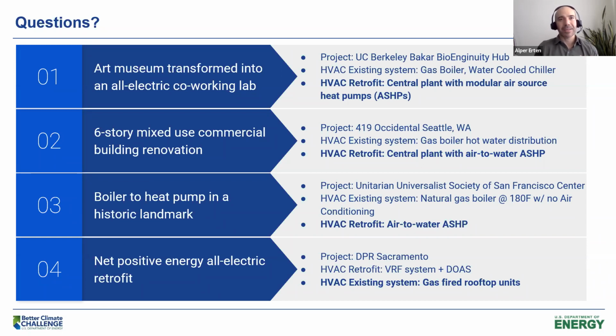In terms of the conversion to electrification for the building plant, there was a water cooled chiller there, so replacing that equipment with air source heat pumps doesn't make a huge difference. Again, this is for a cooling dominated building in a temperate climate. So if you are looking at a colder climate, you may have to add electric resistance backup for heating. That's definitely something to consider for other projects and other locations.